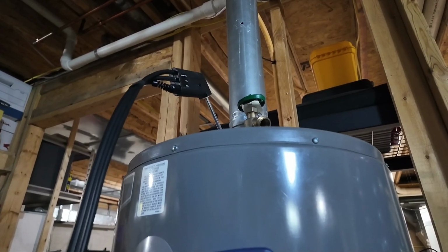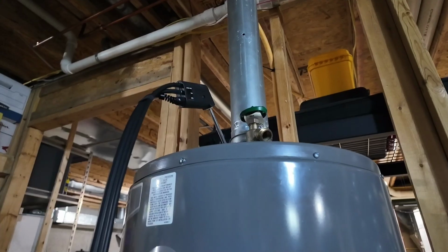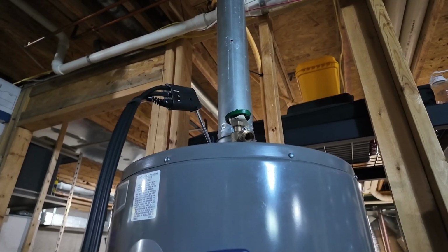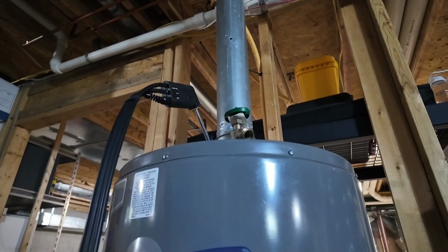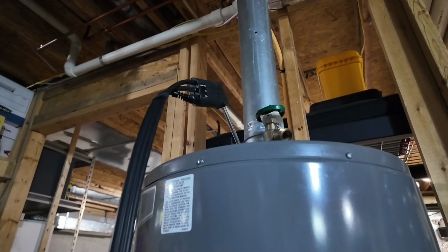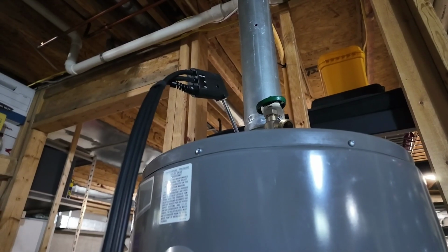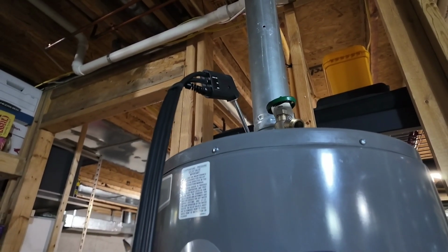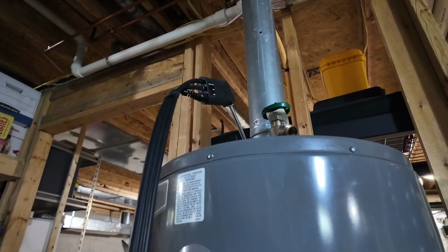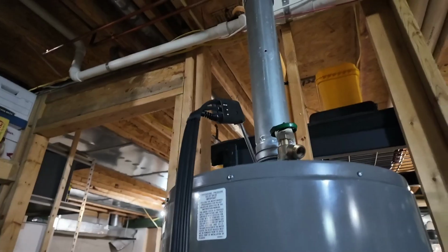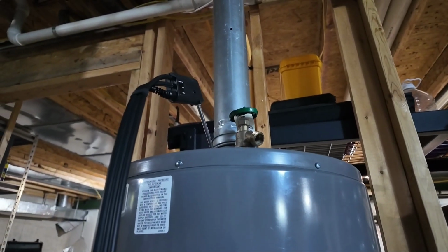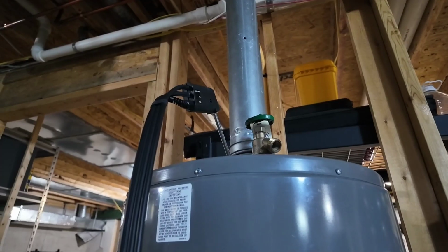I'm going to allow everything to stabilize. We'll see our oxygen levels, O2 levels start to stabilize. Our stack temperature continues to rise, but it'll rise a lot more slowly. Excess air, once it starts to stabilize and our O2 level stabilizes and our temperature stabilizes, then we know we've got a pretty significant, good reading. That is a steady state reading. And it looks like, except for our stack temperature, most everything else has stabilized. We're at 1.5 minutes, so that's 3.5 minutes of operation. We're at 47 parts per million CO air free.